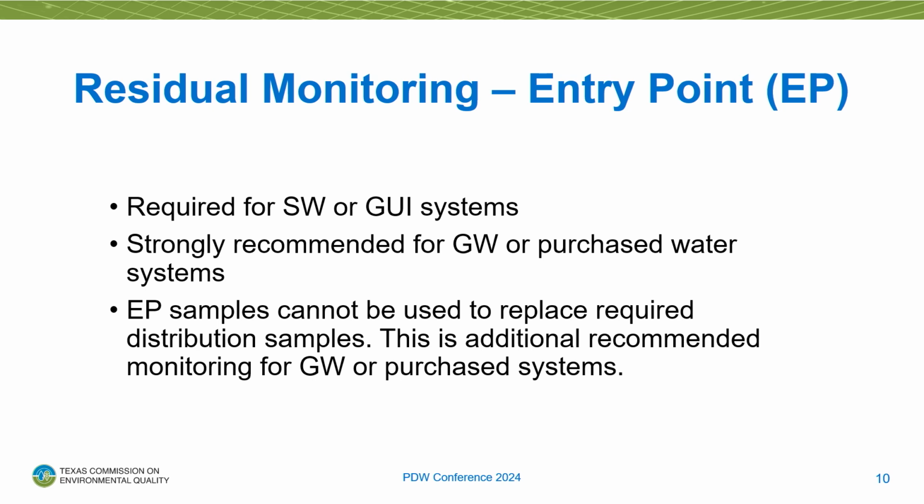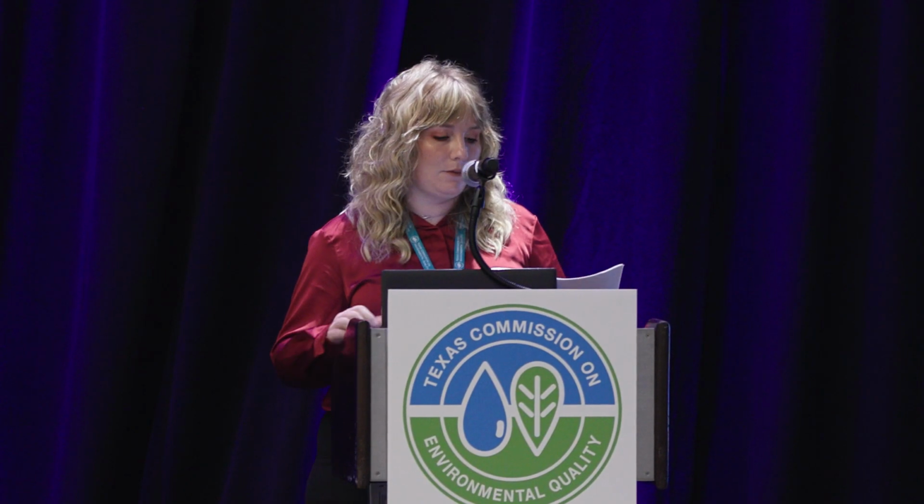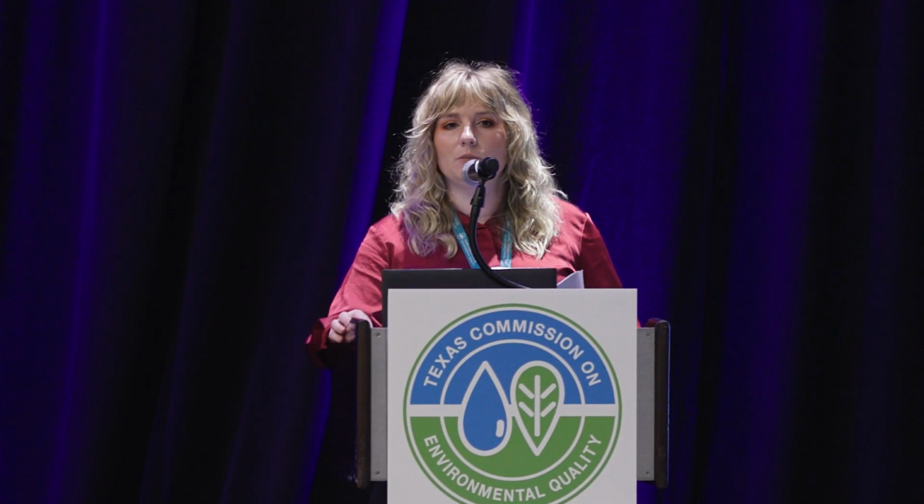This is required for surface water and groundwater under the influence systems. It's not required for groundwater or purchased water, but it is strongly recommended. The distribution only tells you the end of your story. So if you don't measure your disinfectant level leaving your plant, you're not really knowing where you're starting. It benefits you to know what's coming out of your entry point because the entry point is the primary process control point.